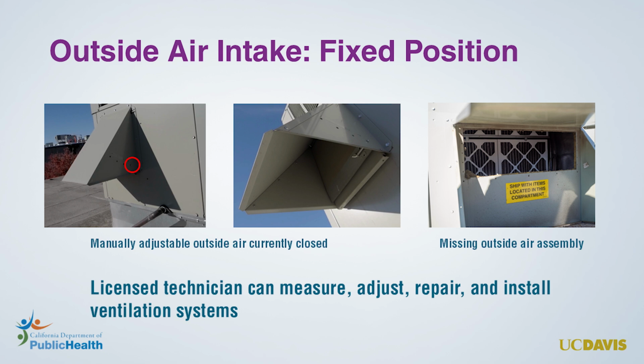In the image on the left, we see a fixed outdoor air intake with an adjustable opening set with a pin, highlighted in red. Currently, the intake is fully closed, meaning there is no outdoor air entering the system. Fixing this requires configuring the outdoor air assembly to achieve the desired outdoor airflow.